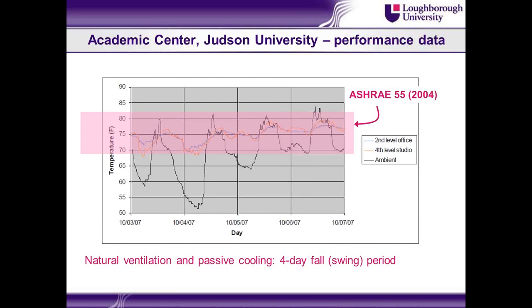Okay, so actual performance data then. This is in the 4-day fall period, what we call a swing period, where we're moving over from mechanical to passive. So we're in passive mode here, October the 3rd through October the 7th. The black line here is the outside temperature going up to 82, a bit higher. And then you can just about make out the orange and the blue, which are the second and fourth floor level temperature sensors. Nice example here of those two phenomena happening. We've reduced the peak temperature and we've time shifted it off to the right. So working very well here in passive cooling mode.